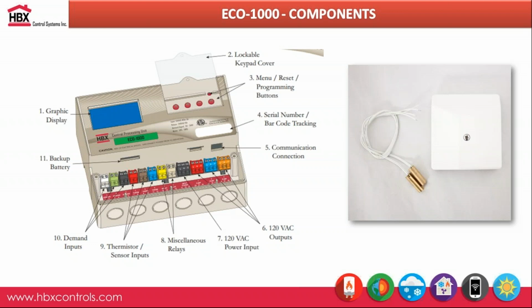The controller utilizes 3 demand inputs for your heating and cooling demands, so you can hook up a thermostat or a 24-volt connection. You can put a jumper wire there to simulate a heating or cooling demand on those demand outputs.